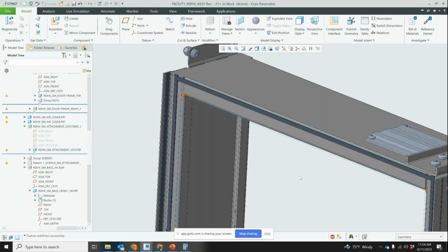Also, I say that because I know the problem with the rear doors. If you use 19-inch racks, the height is always different, the width is always different, the power is always different, the connections for the water are different, and as many differences as you put in there, we will have to develop new rear doors, and the variance is incredibly high.